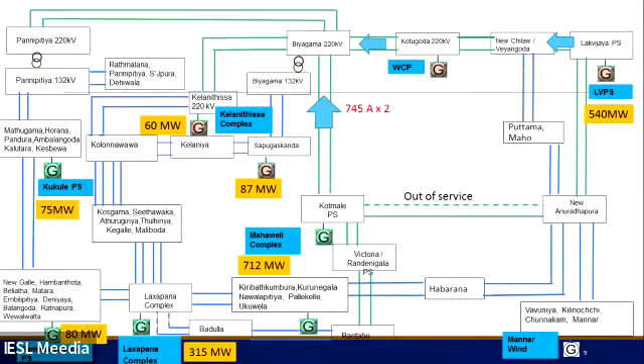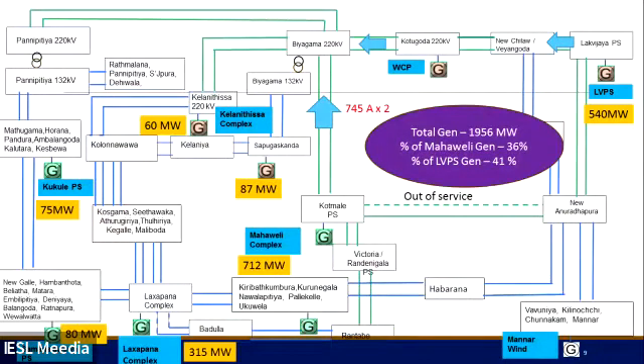Mahaweli generation is running at 712 megawatt. The loading of the two Kotmale-Biyagama circuits is 745 into 2. One Kotmale to Anuradhapura 220 kV circuit, circuit number 1, is out of service at that time, because that line had been released for the New Habarana grid integration project. Lakvijaya is running at 540 megawatt. Since we were running hydro at maximum, Laxapana is also running at 315 megawatt. Total generation was 1,956 megawatt. Mahaweli has 36% and Lakvijaya has 41%, altogether around 77%.